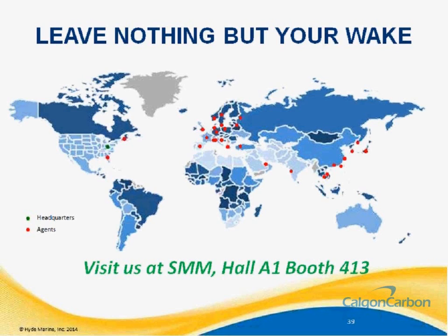Does a bypass valve open upon plant failure? In accordance with the Ballast Water Management Convention, all ballast water treatment systems must be capable of bypassing themselves in the event of an emergency. Our interpretation of that section of the code is that it's up to an owner to decide if they wish to have the bypass valve open or closed during a shutdown or an alarm condition. As we talked about before, allowing this valve to open allows ballast to continue to flow, therefore not creating a dangerous situation on board the vessel. But it does create a situation where there is potentially untreated water going into the ballast tanks, or, in the event of discharge, untreated or partially treated water going overboard from the vessel.